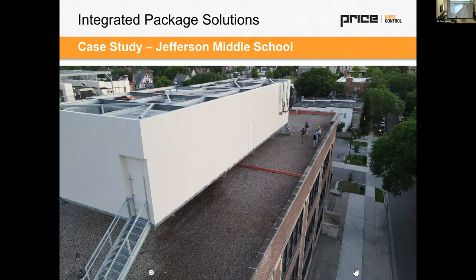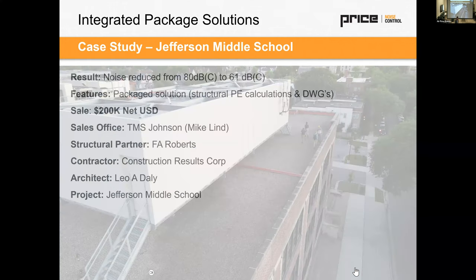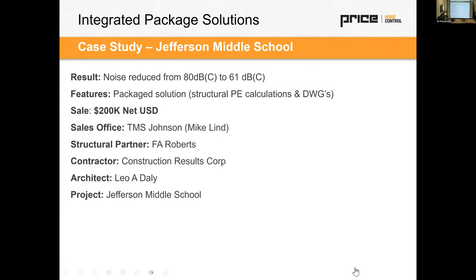And you can see how close the property line is to this equipment. And for whatever reason, they didn't think of sound as part of it. We were able to get it from 80 down to 61 dBc, which 65 was actually what they were shooting for at the property line. And at the homeowner, they wanted to be at 55, which we were able to do. And we worked with the group at TMS Johnson in Minnesota for this one. It was about a $200,000 noise control solution.